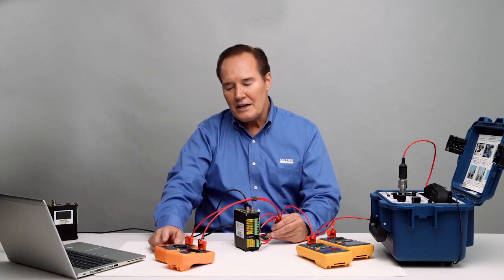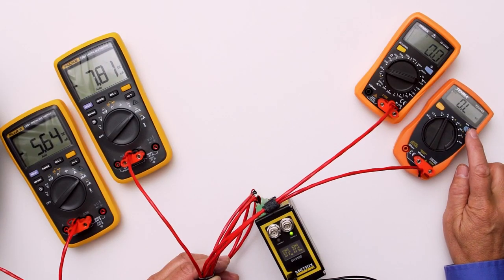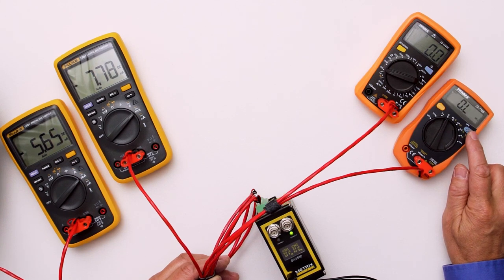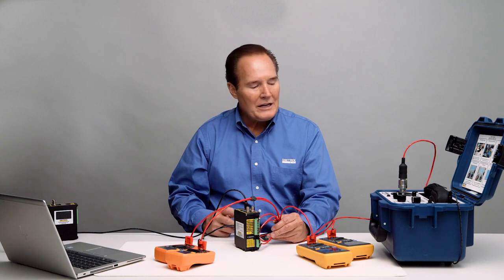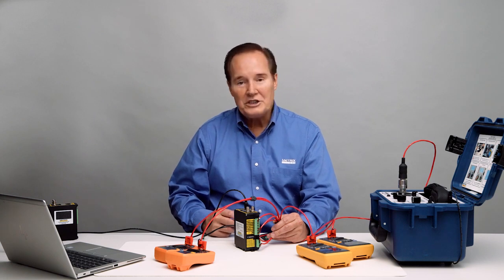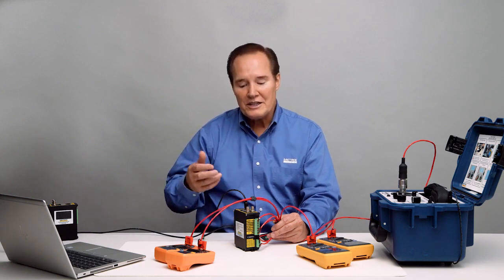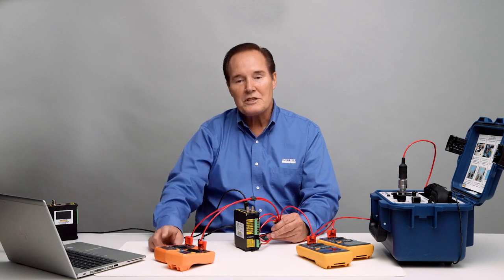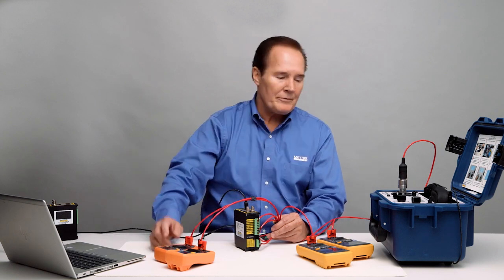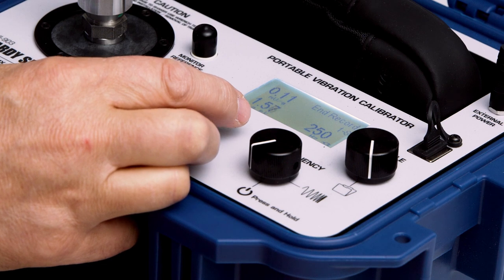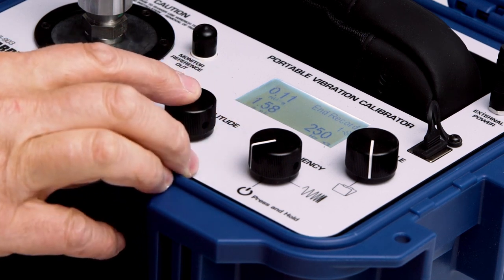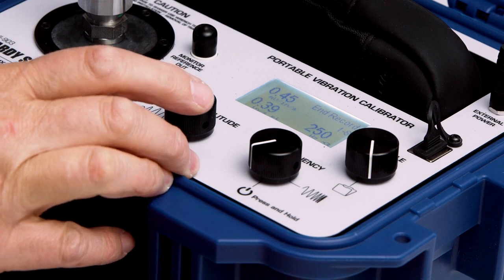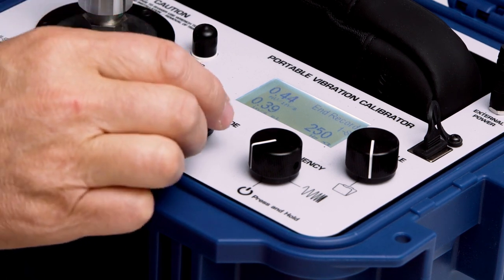You can see that the danger relay hasn't gone yet, and it's still in the OL position, the overload position. So now, as far as an alarm state is concerned, let's go ahead and increase this to 3 Gs, or 3.2 Gs, and get the danger alarm to come in, and we'll see the other relay change state. Oh, what's interesting is the alert just came on for velocity at 250 hertz. And that makes sense because we're up at 0.39 inches per second right now.